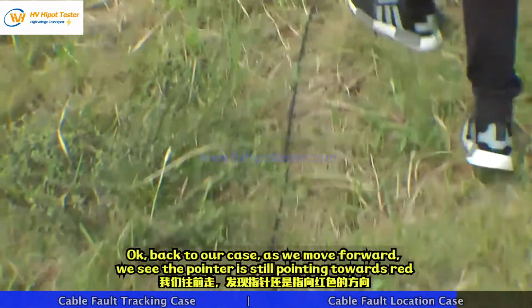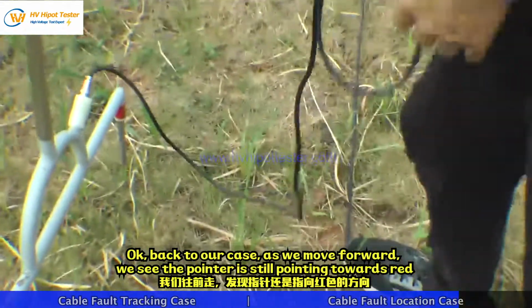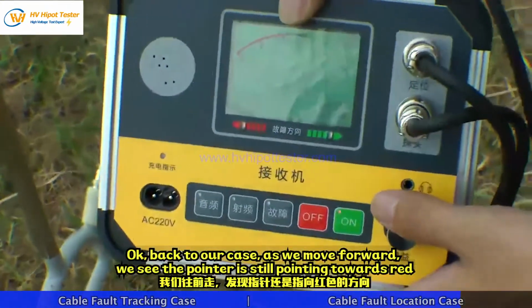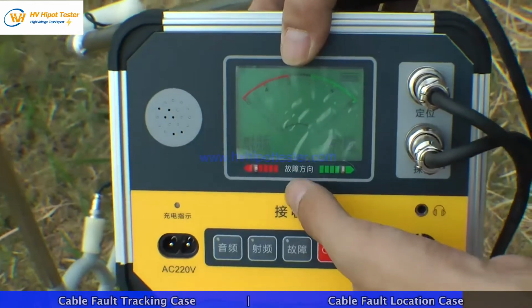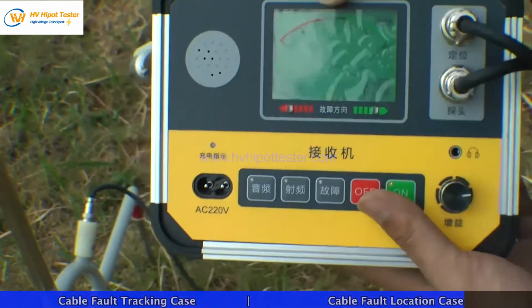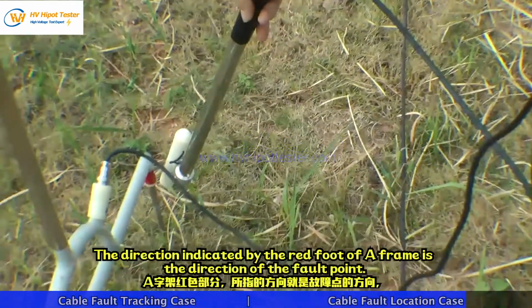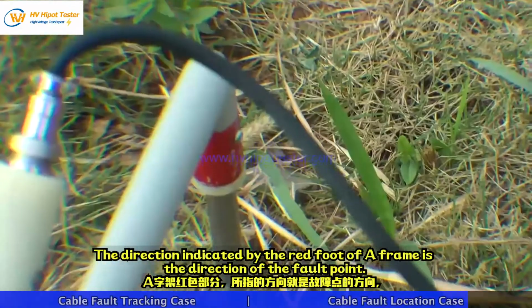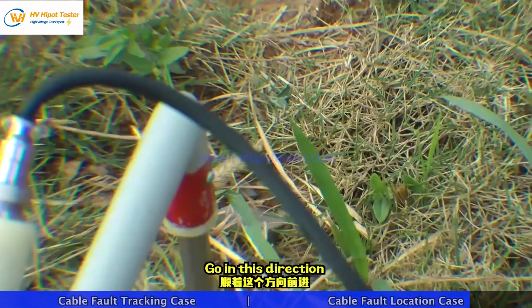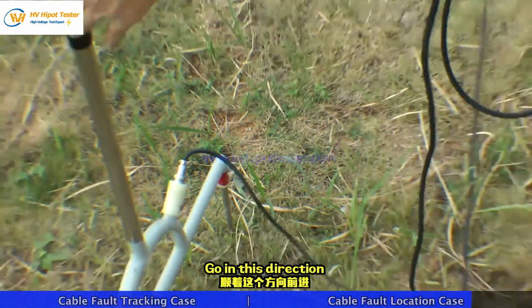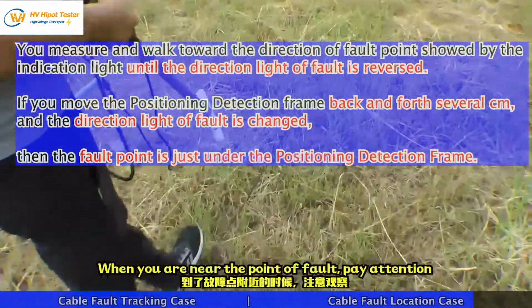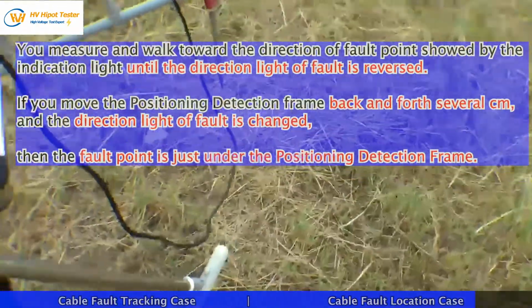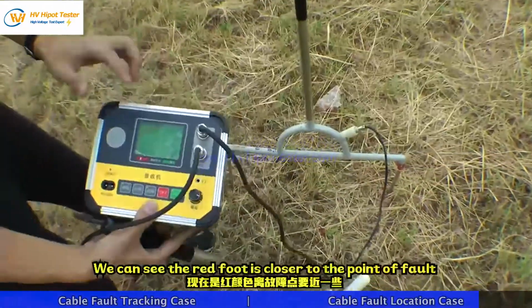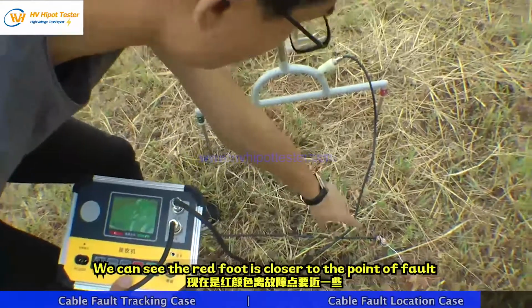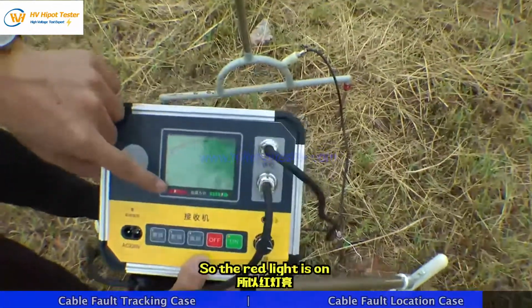Okay, back to our case. As we move forward, we see the pointer is still pointing towards red. The direction indicated by the red foot of the frame is the direction of the fault point. Go in this direction. When you are near the point of fault, pay attention. We can see the red foot is closer to the point of fault, so the red light is on.